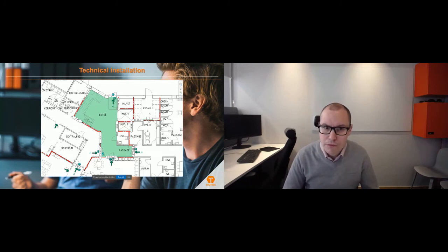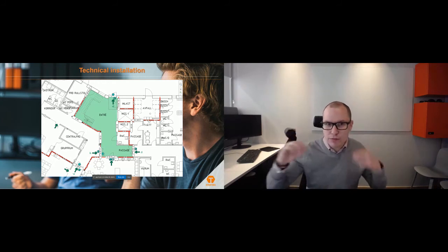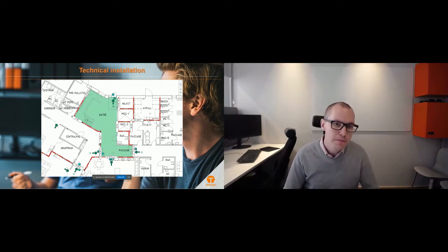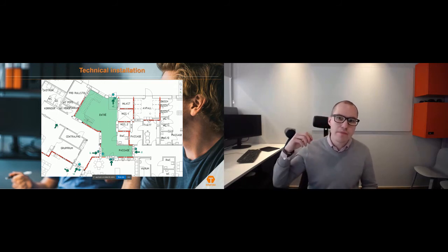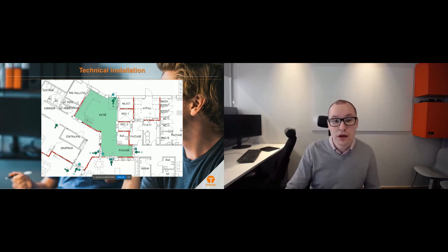minutes. And cables, as most of you know, aren't really drawn in a 3D model. They're just a connection to enable electrical calculations. But here you can actually check that those objects, between those two points that go in and out of these kinds of spaces with these kinds of requirements, fulfill them. And you can use it on the construction site for quality assurance as well, checking off that we have actually put in a fire-resistant cable in these areas. It's a very common problem.